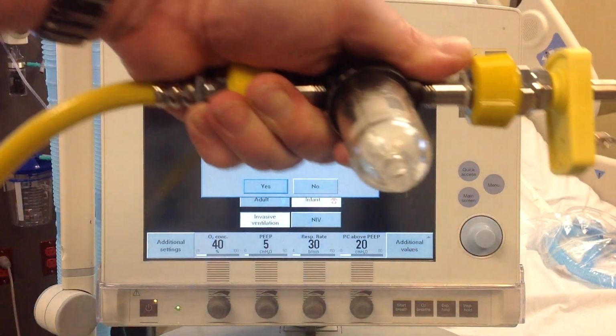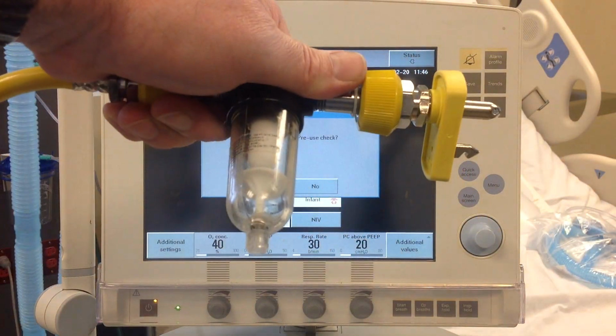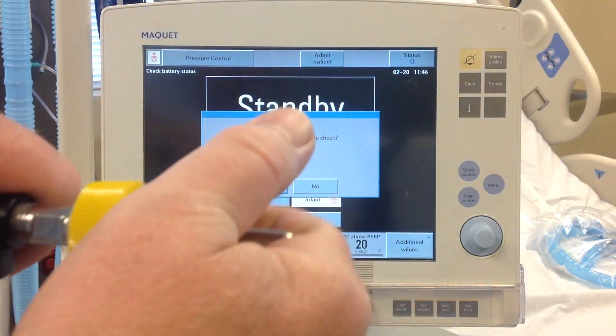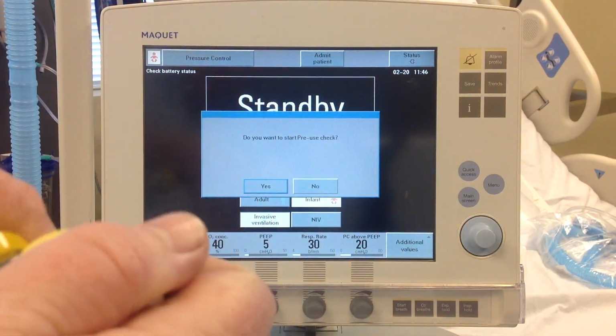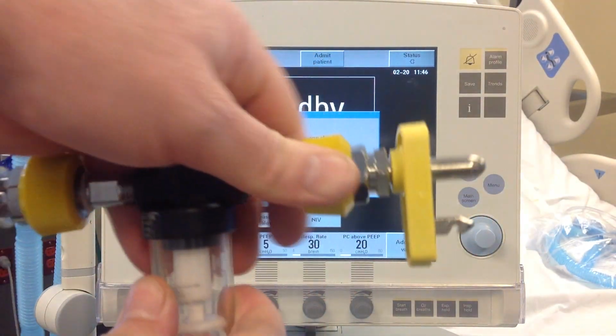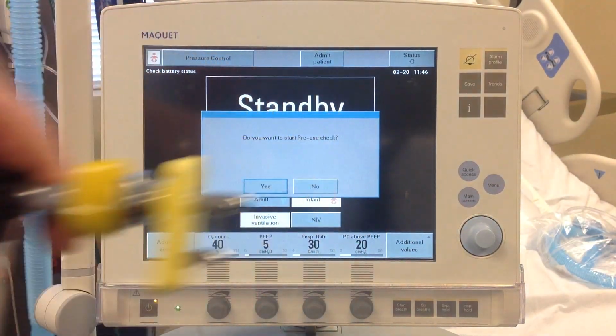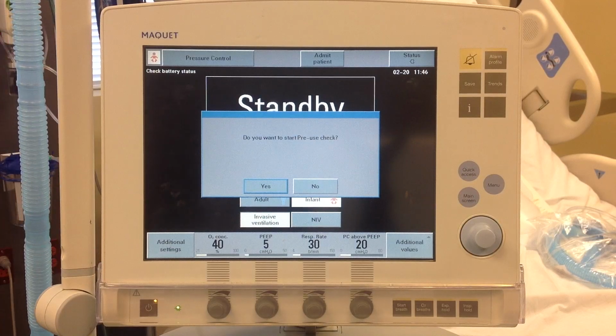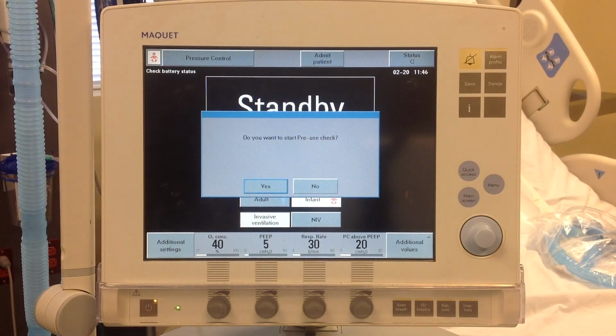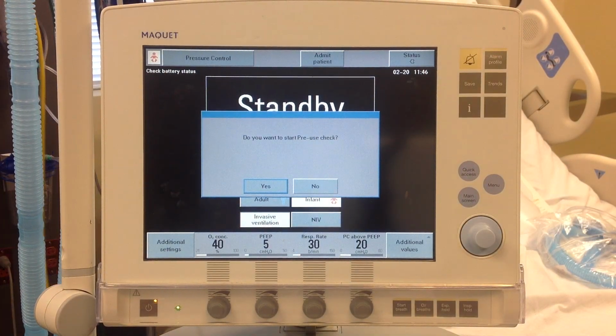When I just found this hooked up to the wall, it was hooked up like this. Now, the water trap is not going to be effective if it is on its side. So we need to have it straight up and down with the plugs here, and this needs to be straight up and down on the wall. So if there's any water, it'll go into it. So I'll plug that back in.